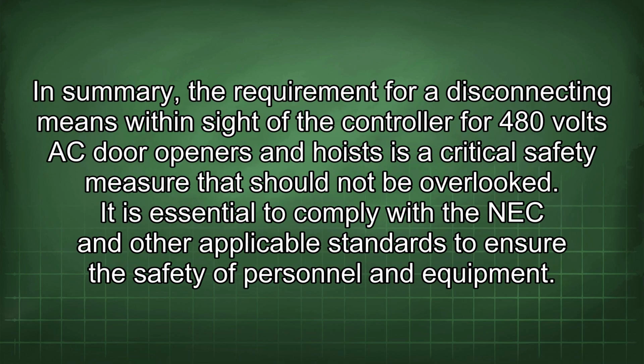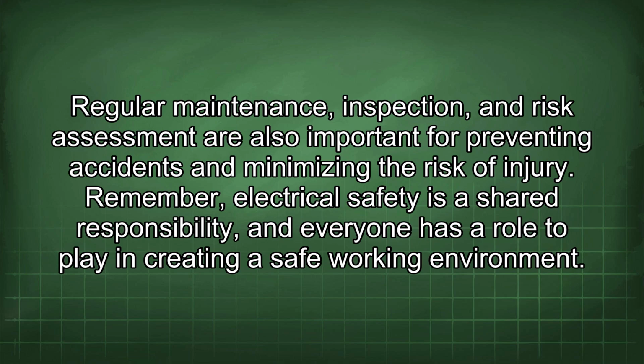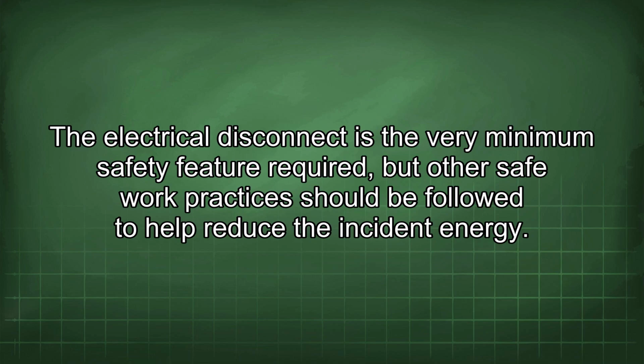In summary, the requirement for a disconnecting means within sight of the controller for 480 volts AC door openers and hoists is a critical safety measure that should not be overlooked. It is essential to comply with the NEC and other applicable standards to ensure the safety of personnel and equipment. Regular maintenance, inspection, and risk assessment are also important for preventing accidents and minimizing the risk of injury. Remember, electrical safety is a shared responsibility, and everyone has a role to play in creating a safe working environment. The electrical disconnect is the very minimum safety feature required, but other safe work practices should be followed to help reduce the incident energy.